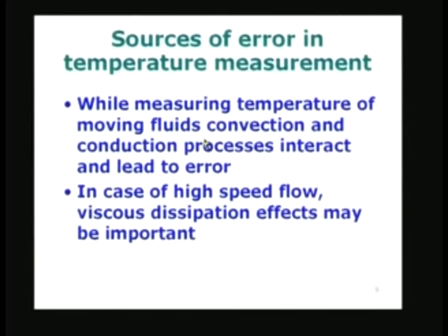While measuring temperatures of moving fluids, convection and conduction processes interact, and therefore they lead to systematic error. In the case of high speed flow, which is involved in aerospace applications, viscous dissipation effects may also be important. That means the conversion of kinetic energy of the fluid to internal energy, and when kinetic energy is converted to internal energy because of viscous forces, the temperature will go up.